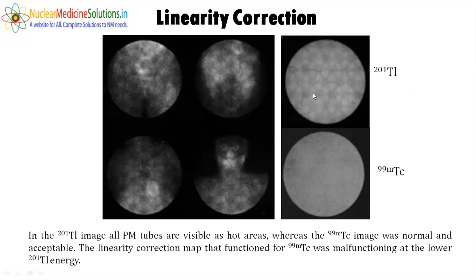And you create a linearity correction map for each radionuclide. You cannot use a technetium linearity correction map for thallium-201. Otherwise, what will happen? This linearity correction map will not work for thallium-201, and due to this, it will produce non-uniformity in the image, or you can say a cold spot in the image.